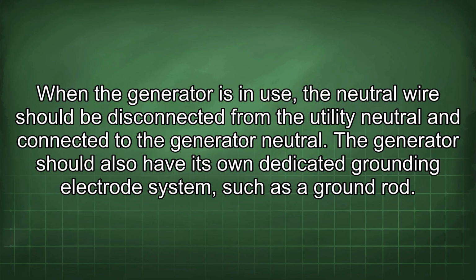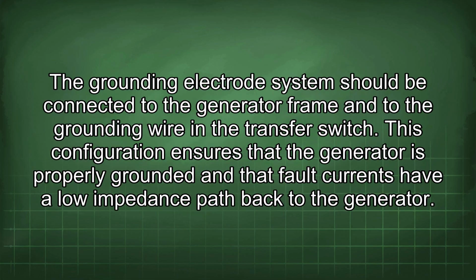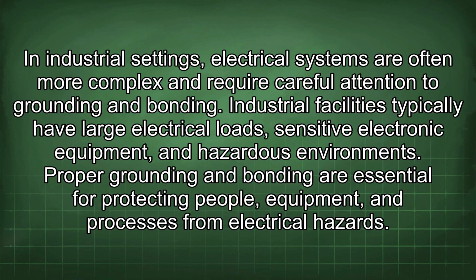When the generator is in use, the neutral wire should be disconnected from the utility neutral and connected to the generator neutral. The generator should also have its own dedicated grounding electrode system, such as a ground rod. The grounding electrode system should be connected to the generator frame and to the grounding wire in the transfer switch. This configuration ensures that the generator is properly grounded and that fault currents have a low impedance path back to the generator. In industrial settings, electrical systems are often more complex and require careful attention to grounding and bonding.